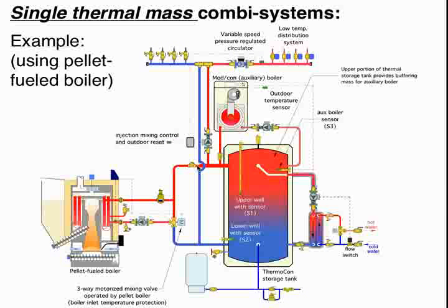So, okay. All right. Another question, when we're doing space heating, I suppose chilling as well, or cooling, no domestic hot water in the picture. If you're just thinking from a controls standpoint, is it typically better to maintain your buffer tank temperature always, or based on first demand or some type of setup like that? Yeah, again, that's a tough one. You really got to look at what the load profile looks like. If it's a load where you're expecting a lot of, I'll say, frequent small demands for heating, it may be justified to maintain the buffer tank.